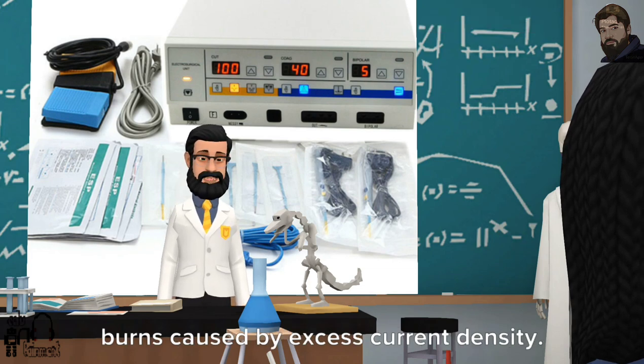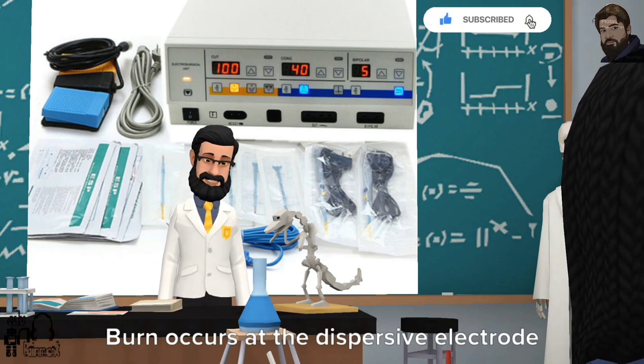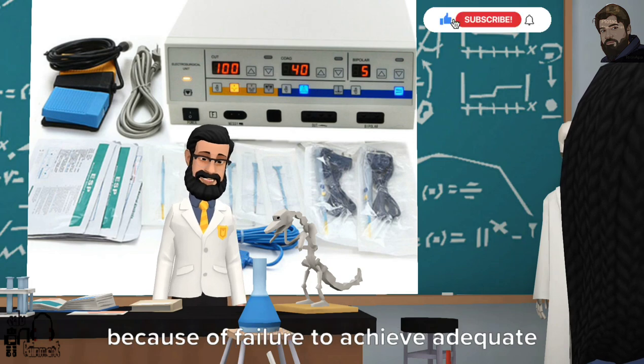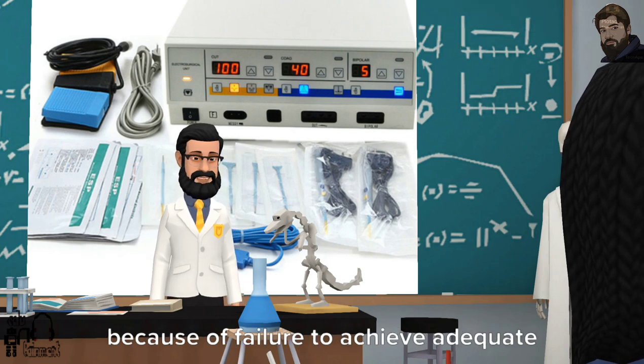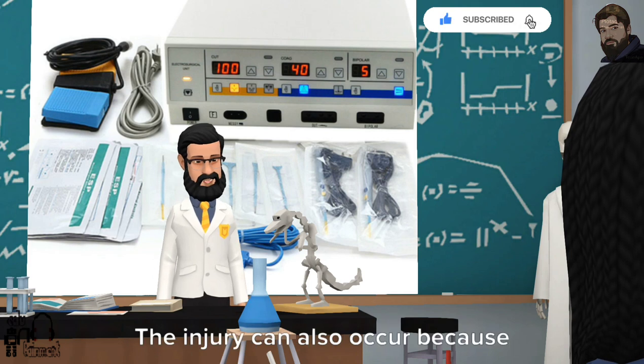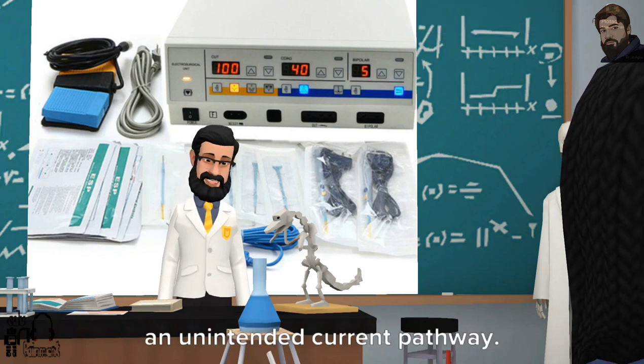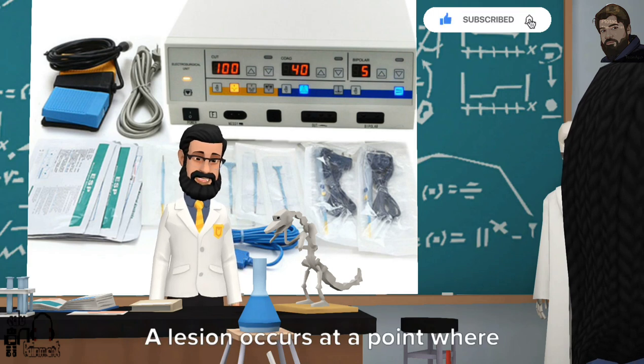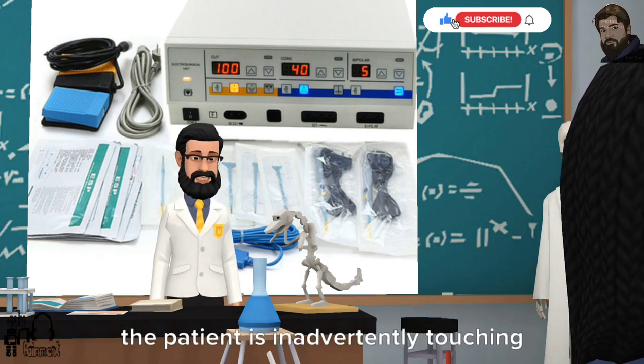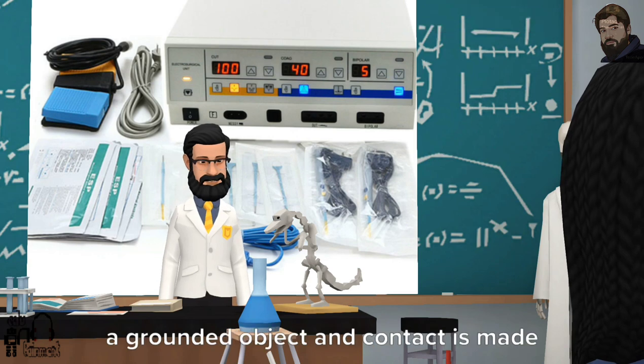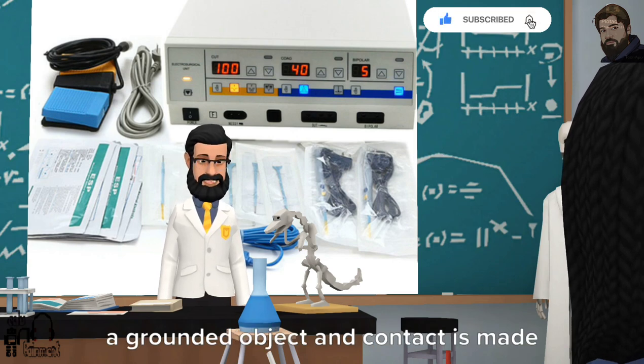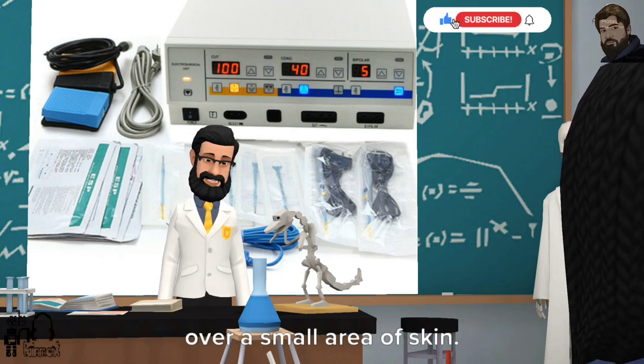2. Burns caused by excess current density. 3. Burn occurs at the dispersive electrode because of failure to achieve adequate contact. 4. The injury can also occur because of an unintended current pathway. 5. A lesion occurs at a point where the patient is inadvertently touching a grounded object and contact is made over a small area of skin.